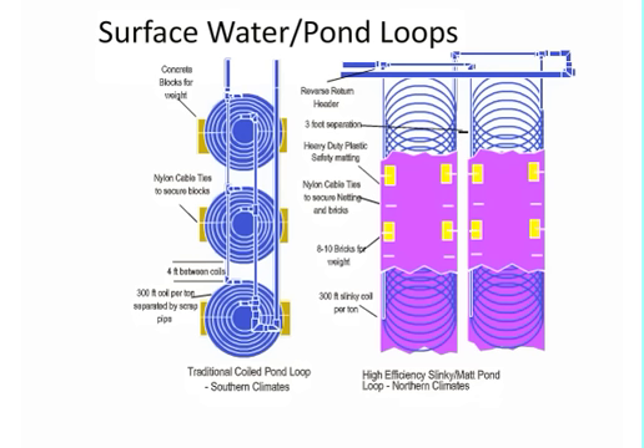Here's a couple of examples of pond loop heat exchangers. The one on the left is your typical 300-foot coil - this is an old drawing and there's some things about it I don't prefer, I want to address that. It shows the concrete blocks or weight attached to the actual coil. You'll see some pictures later; I'm not a fan of that.